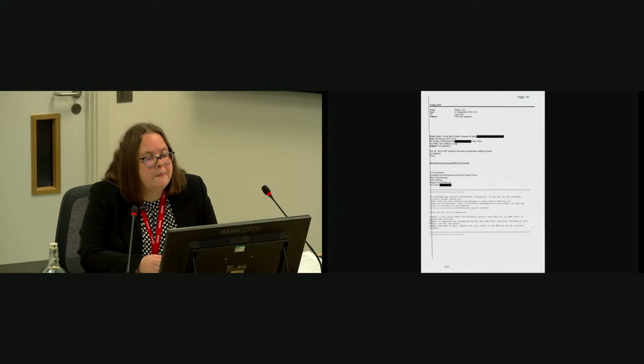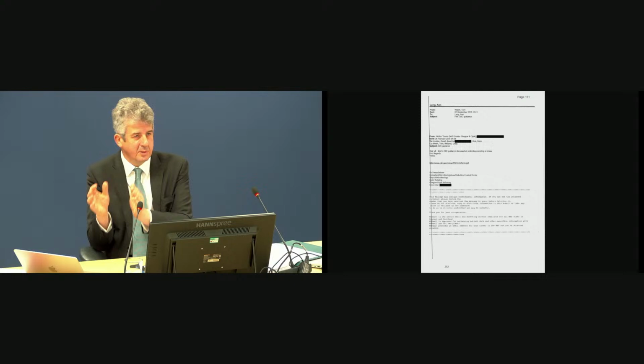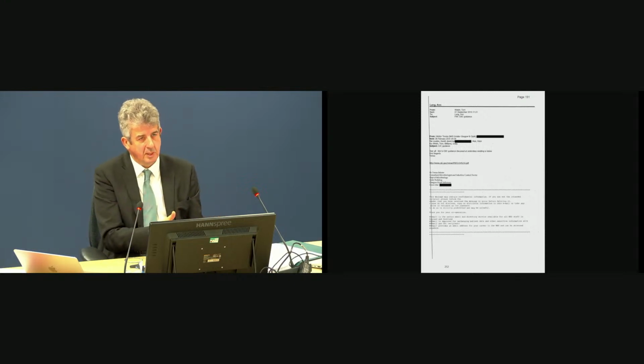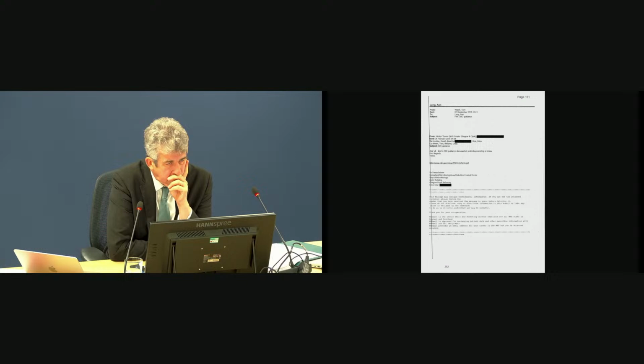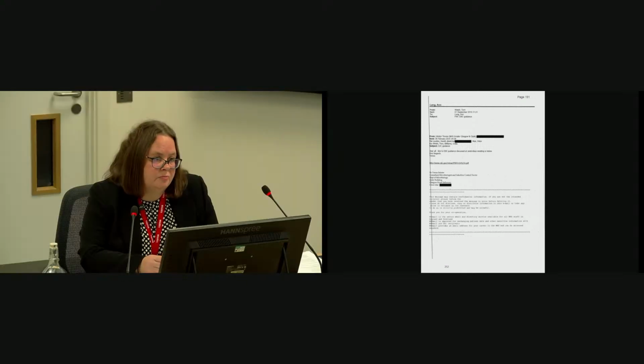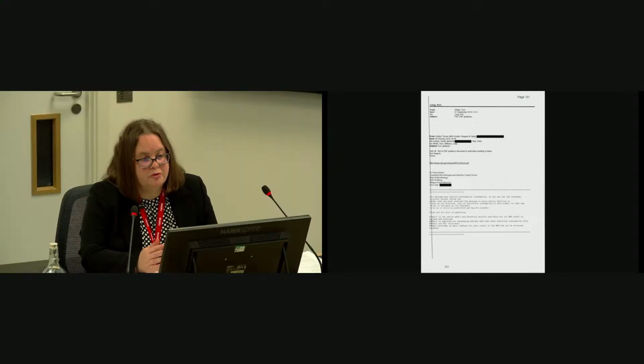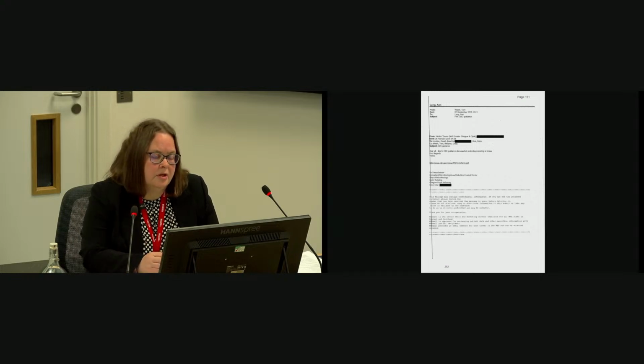So can you explain for the benefit of us, what's the difference between the rooms in the Beatson and the rooms that are being talked about in this context in February 2015? So the rooms in the Beatson were sort of traditional positive pressure rooms. So it was just a room at positive pressure, usually. So that means the air is at a higher pressure in the room, so it's pushing outwards. Yes, so the air's coming out. They were HEPA filtered, they had a higher change rate. These were a different style of room. These were the PPVL rooms. So the room itself is at a neutral pressure, and it's the lobby that's at the positive pressure.